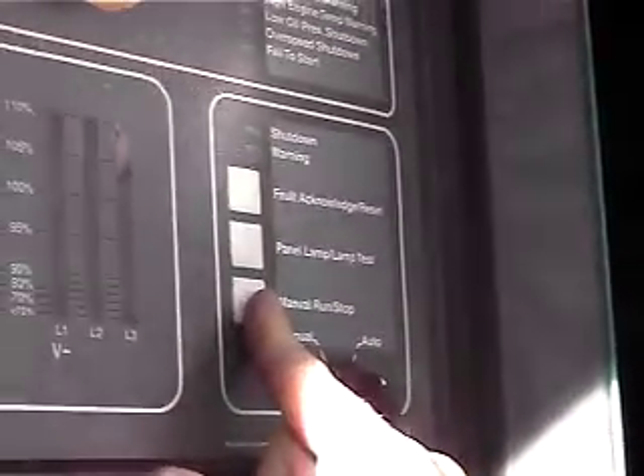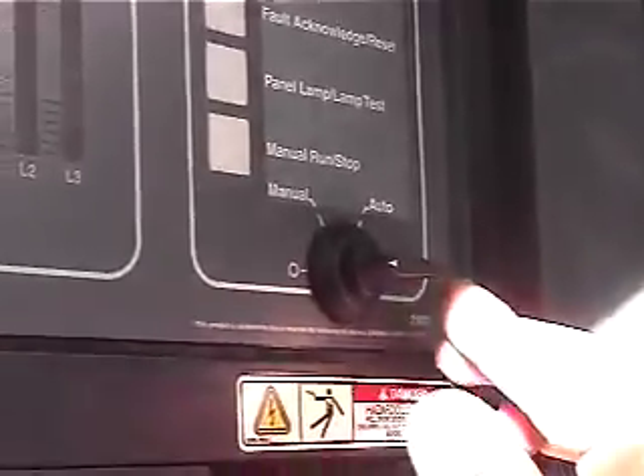So from this point, if you wanted to start it manually, you can flip it to manual and push this manual run stop button. Okay, that'll start it. It'll stay in that mode until you tell it to stop. To tell it to stop, you can push the button a second time, or you can turn the switch back to auto. If you turn the switch back to auto, it'll drop down to an idle and run for 2 minutes, and then it'll shut off. If you want it to shut down immediately, you can just flip the switch all the way to the left, to the off position.